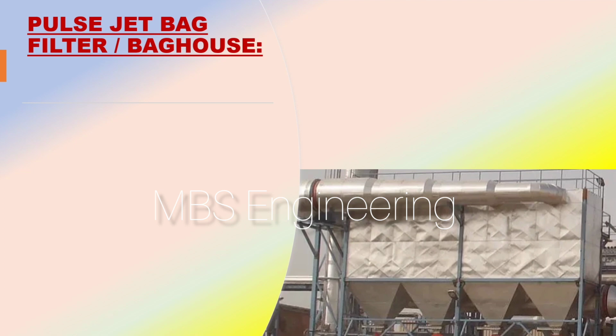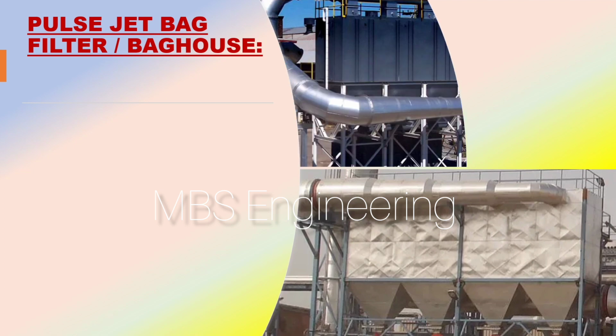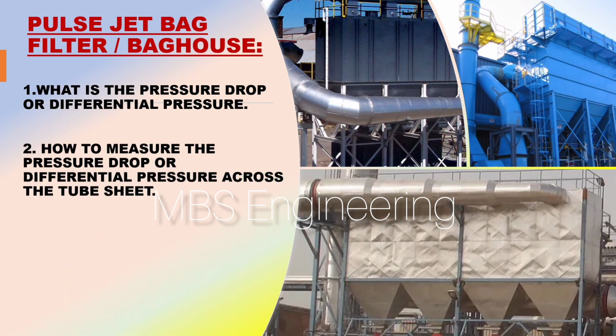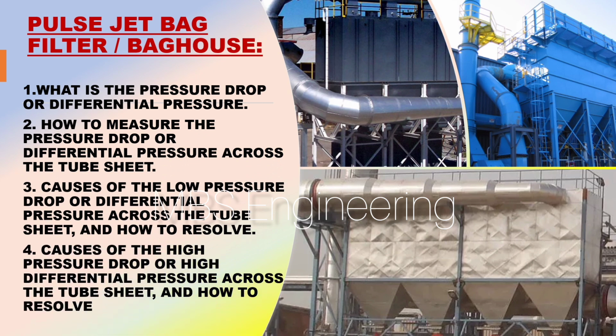First, we understand the working principle of the baghouse. In the pulse jet dust collector, the dusty airstream usually enters from below the bags or filters. It is pulled upwards through the filters, where dust is captured on the exterior surface, and the pulse jet dust collector cleaning system removes particulate matter and dust from the surface of internal filter media with bursts of compressed air.